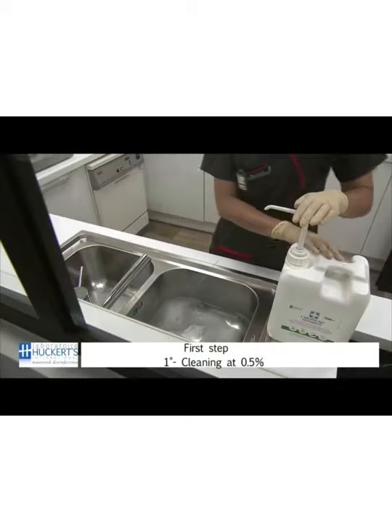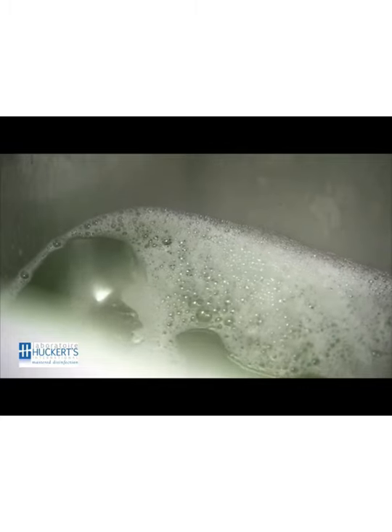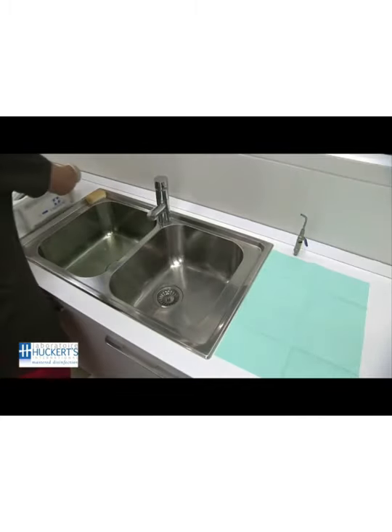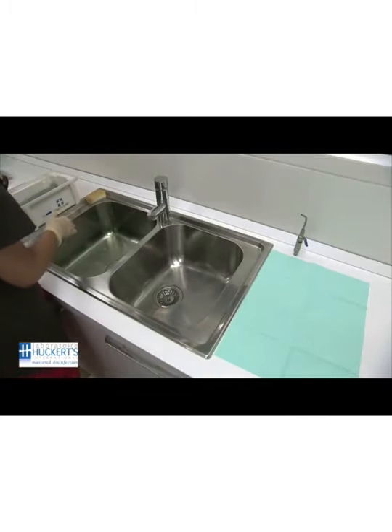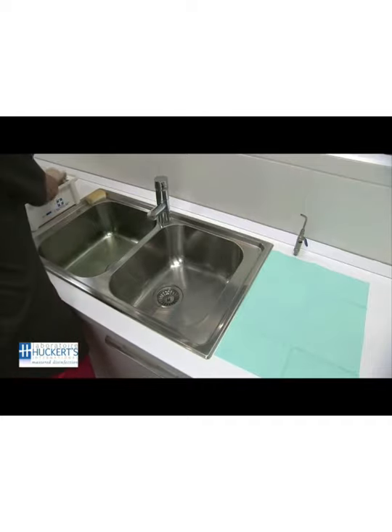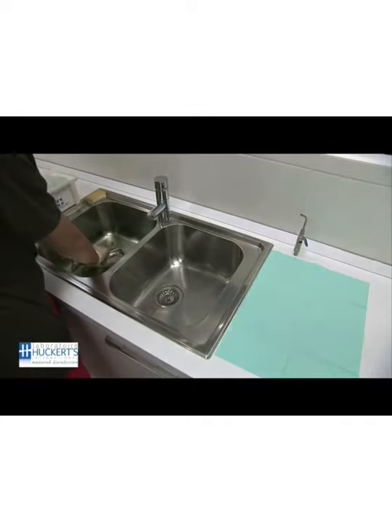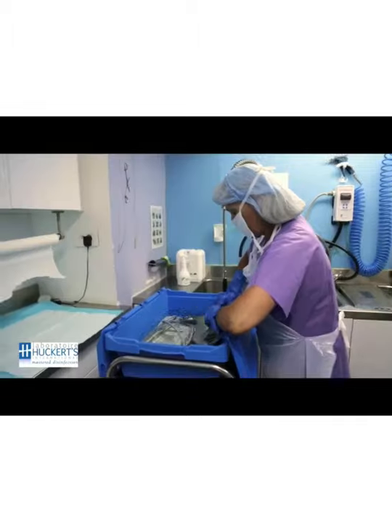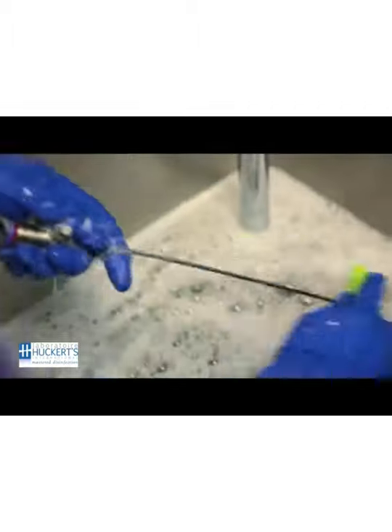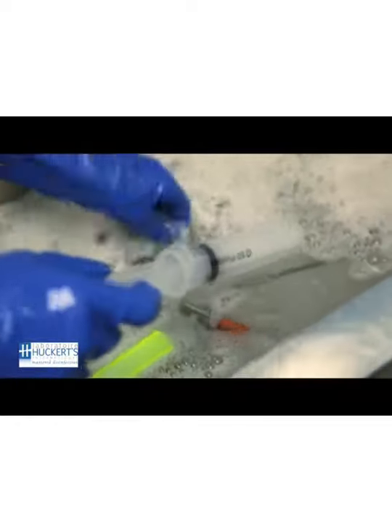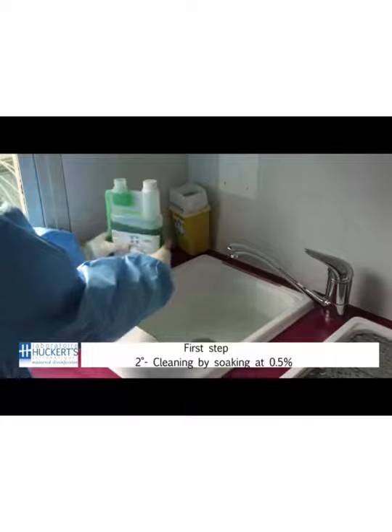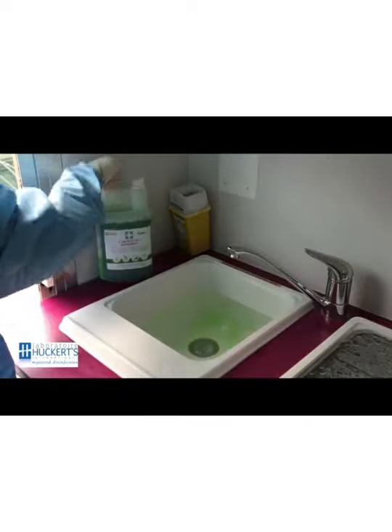Before the required instruments are transferred into the oven, thorough cleaning is required before high-level disinfection and sterilization, because inorganic and organic materials that remain on the surfaces of instruments interfere with the effectiveness of these processes. Also, if soiled materials dry or bake onto the instruments, the removal process becomes more difficult and the disinfection or sterilization process less effective or ineffective at all.